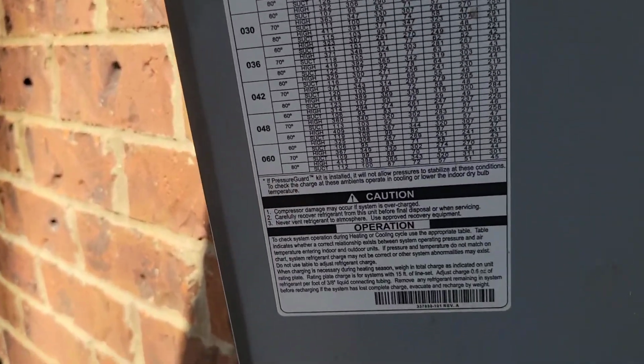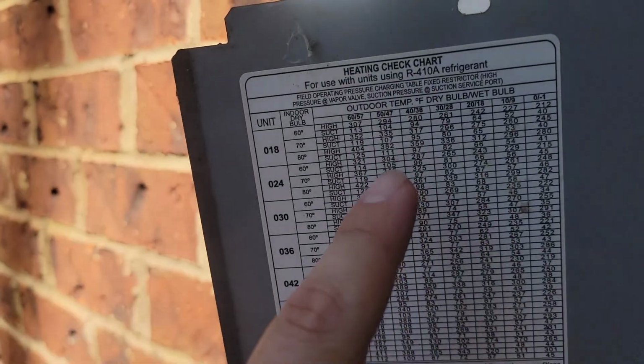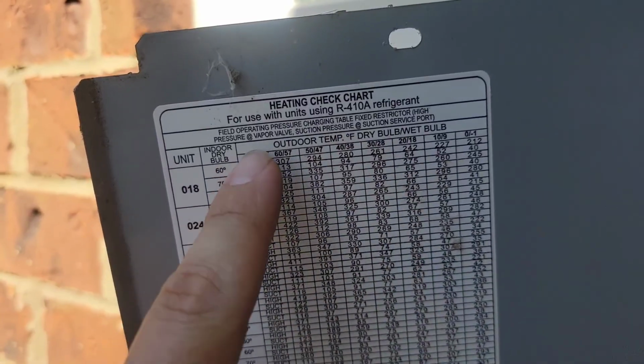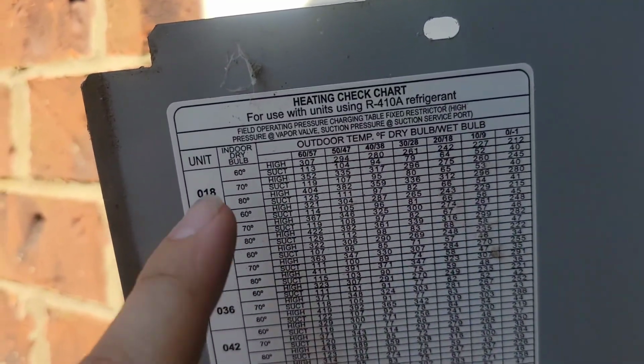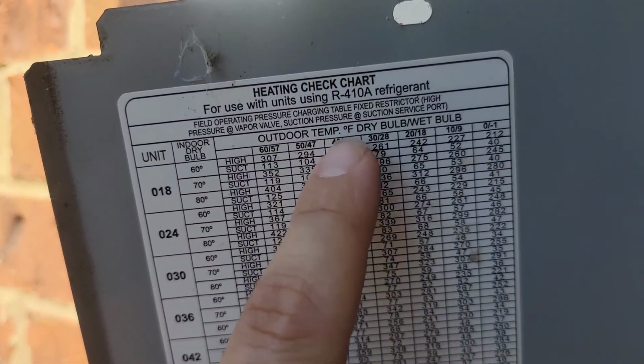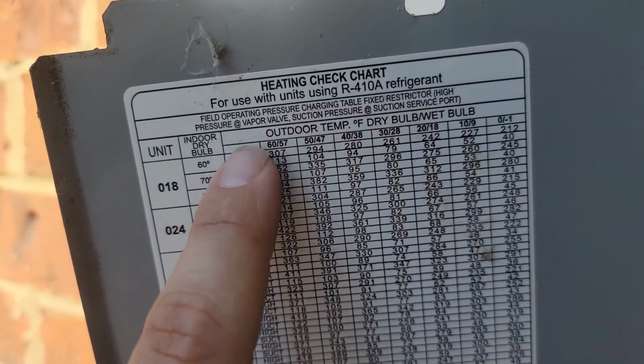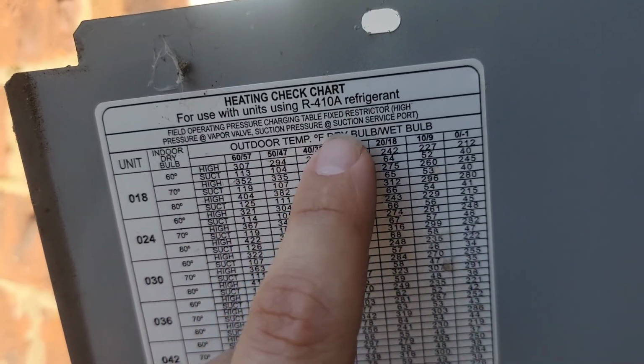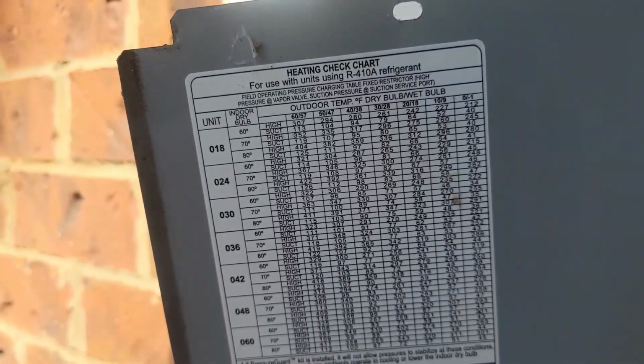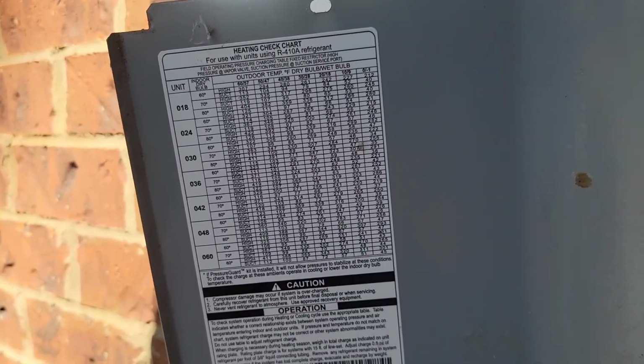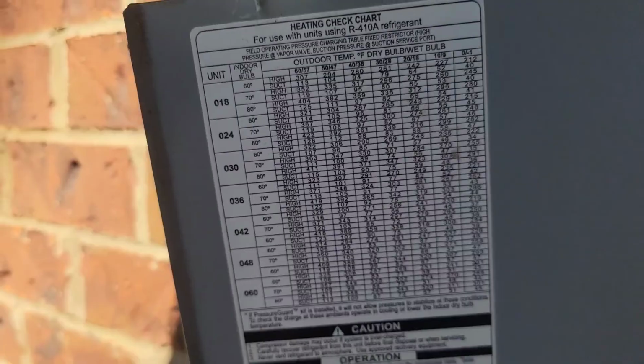Definitely utilize this chart. Make sure that it is for heating or cooling. It says heating check chart. For use with units using 410A refrigerant, field operating pressure, charging table, fixed restrictor, high pressure at vapor valve, suction pressure at suction service port. So make sure you know how to hook up your gauges correctly too. But that's pretty close to what we had.